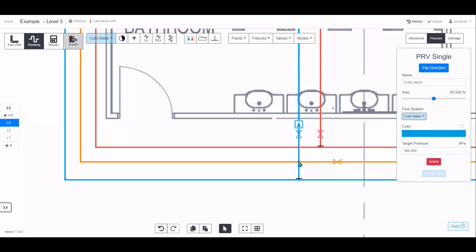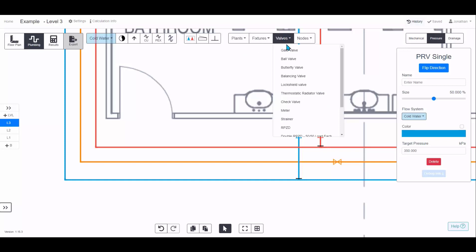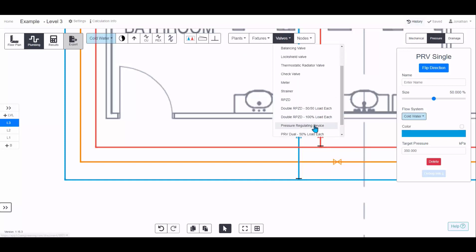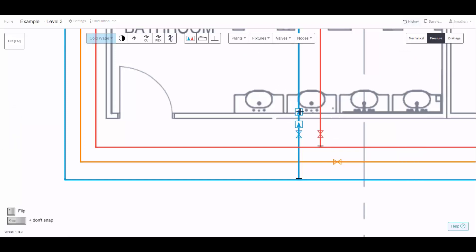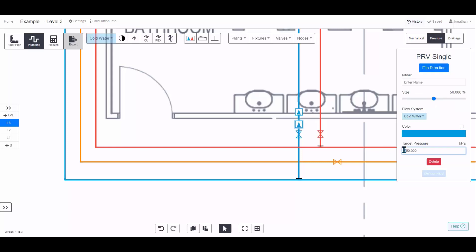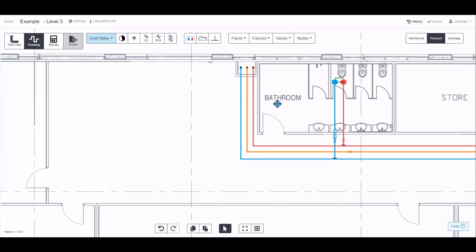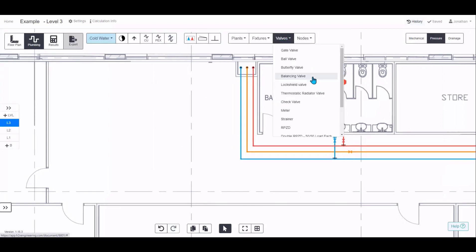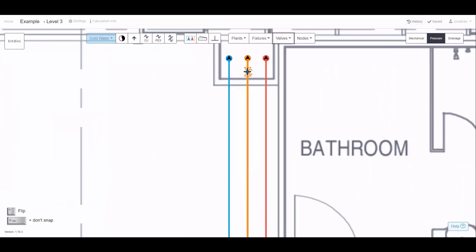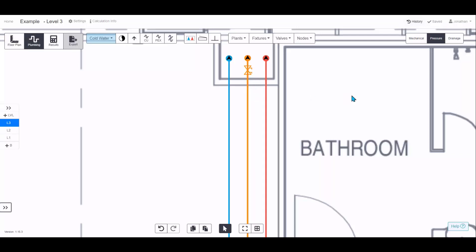If incoming pressure is very high and you're stepping it down too much, you'll get a warning. In that case, place multiple pressure regulating devices in series — step down to 500 kPa with the first one, then down to 350 kPa with the second, so you're not dropping too much pressure at once. There's also a balancing valve: any time two systems interconnect, add a balancing valve to balance the whole system.